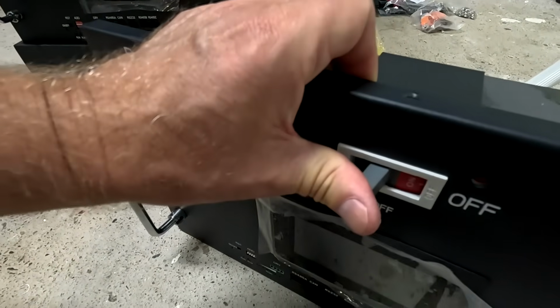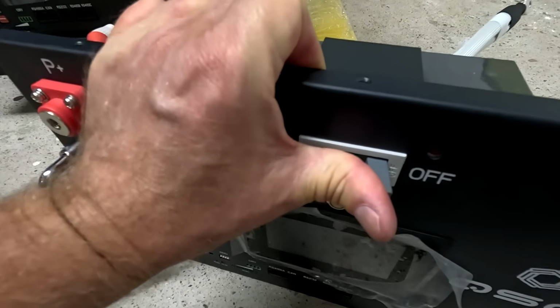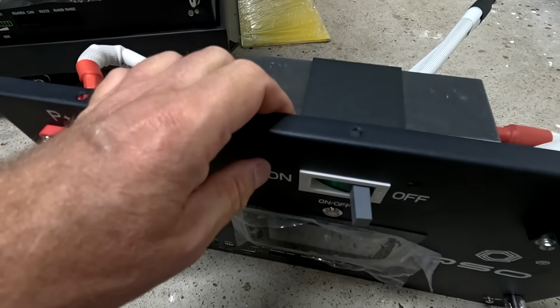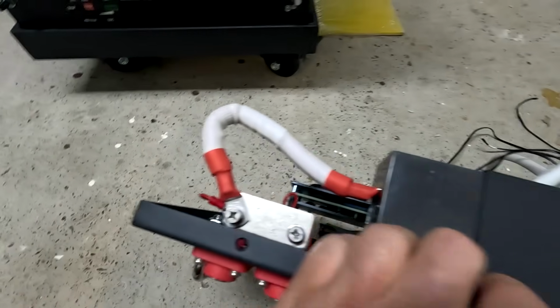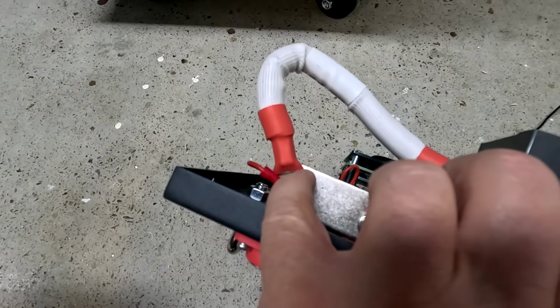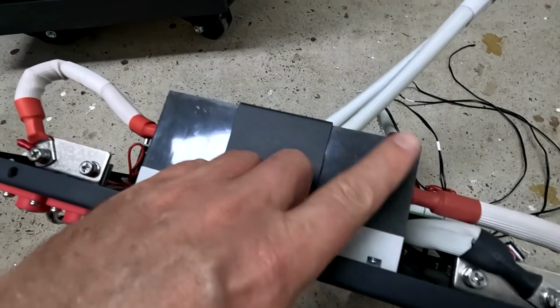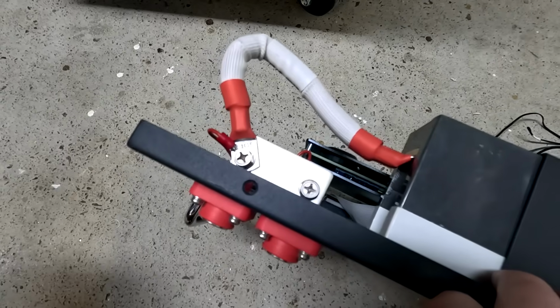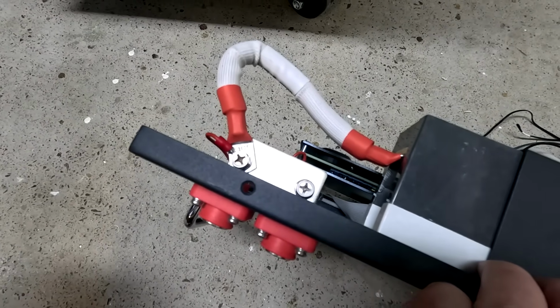Just imagine you want to do a firmware upgrade or something and you want to disconnect this battery from the rest of your system. Well, you would flip the circuit breaker to the off position and it will also turn off your BMS then. So that is not great. So this needs to change either on the other side or directly to the battery. Cannot be on the output side of the circuit breaker.